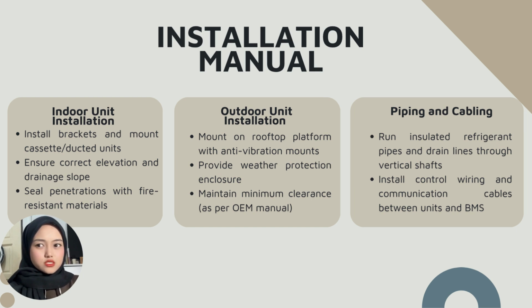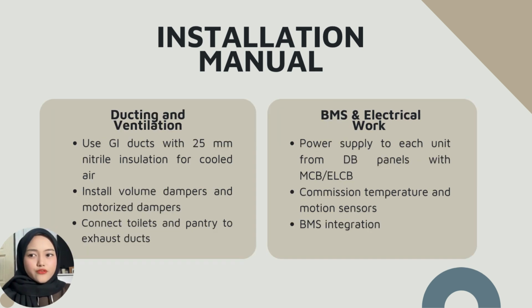For outdoor unit installation, we mount on rooftop platform with anti-vibration mounts, provide weather protection enclosure, and maintain minimum clearance as per OEM manual. And for piping and cabling, we run insulated refrigerant pipes and drain lines through vertical shaft. And we install control wiring and communication cable between unit and BMS. For ducting and ventilation, we use GI ducts with 25 mm nitrile insulation for cool air. We install volume dampers and motorized dampers. And we connect toilets and pantry to exhausts.